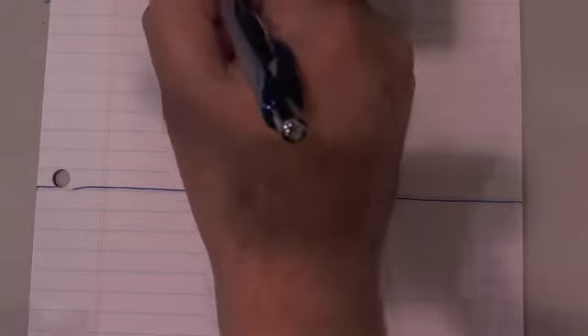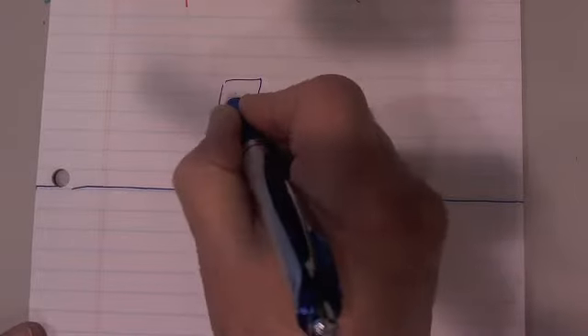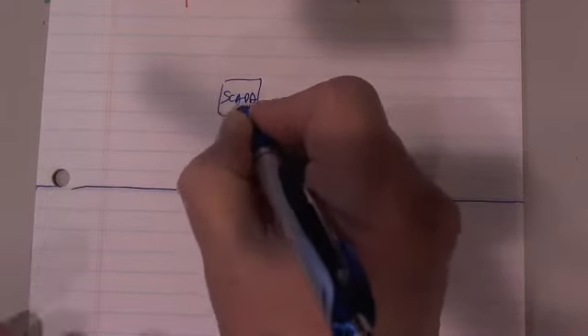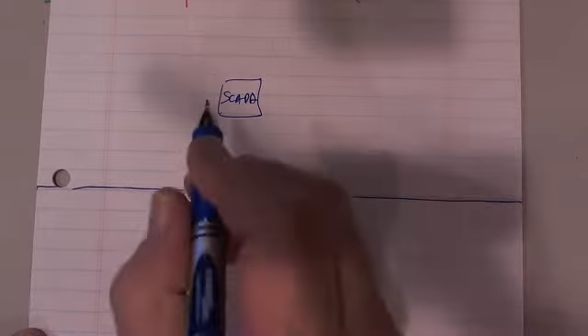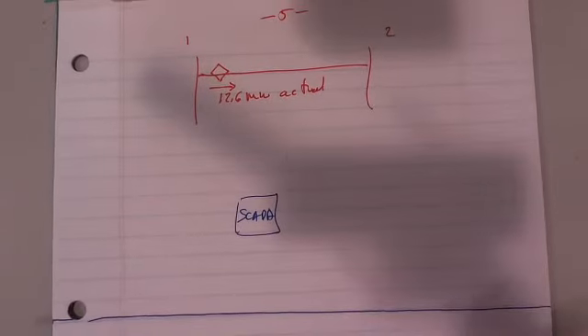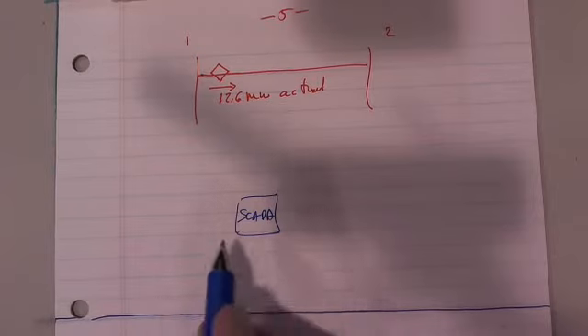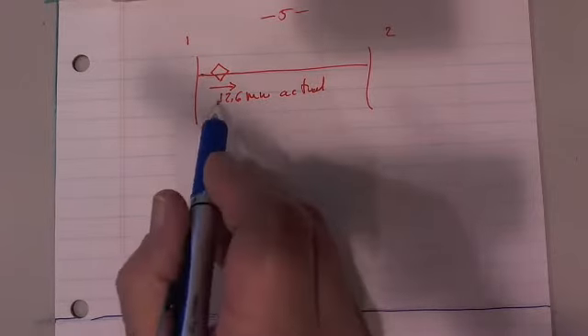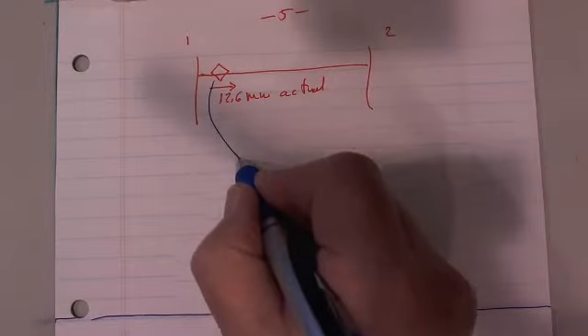Then the state estimator says, okay, the SCADA system - and what a real SCADA system does - by the way, that stands for Supervisory Control and Data Acquisition. Supervisory control is the ability of people to send a coded message to the substation to open a breaker or change a transformer tap, to control something. Data acquisition is just go out and read something. So it goes out and it reads.